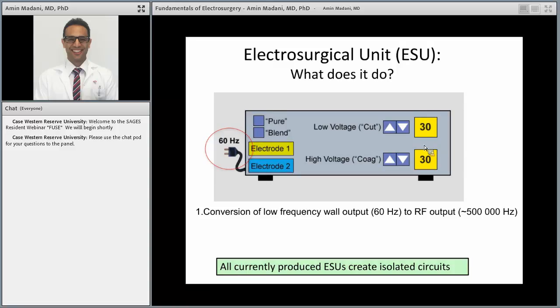Second thing is, when you ask somebody to change the number on the device to, say, put it on cut 30 or coag 30, you're actually asking them to change the power, the amount of energy per unit time, joules per second. So in this case, you're asking them to put it to 30. That's the amount of energy per unit time. And notice, the important thing here is cut and coag, both of them are 30. They're delivering the same amount of energy per unit time. There's no difference between their power here.